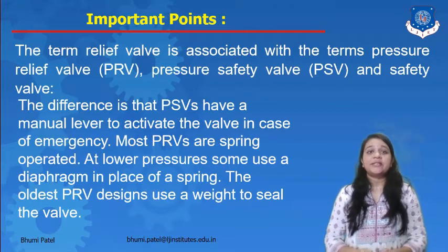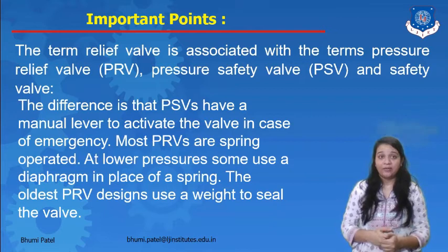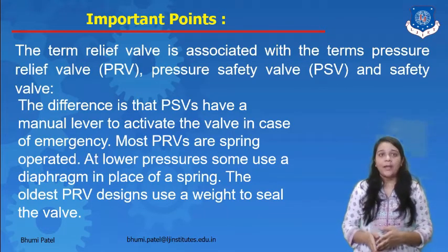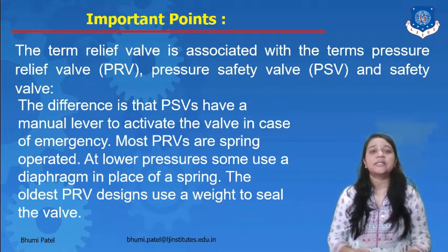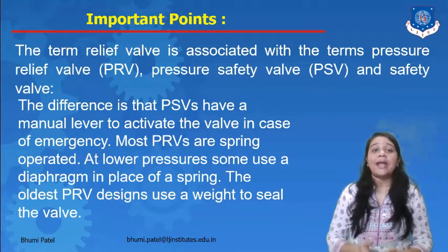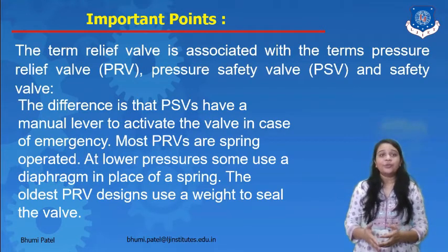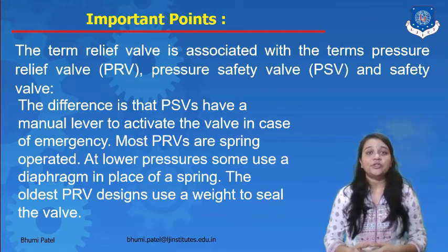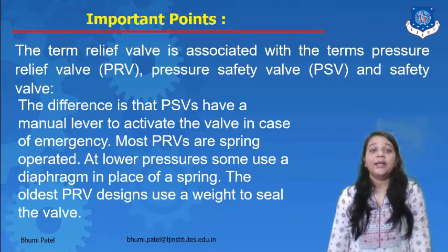The difference is that pressure safety valves have a manual lever to activate the valve in case of emergency. Most pressure relief valves are spring operated, but at lower pressure, some safety valves use a diaphragm in place of the spring. The oldest pressure relief valves were designed to use a weight to seal the valve.